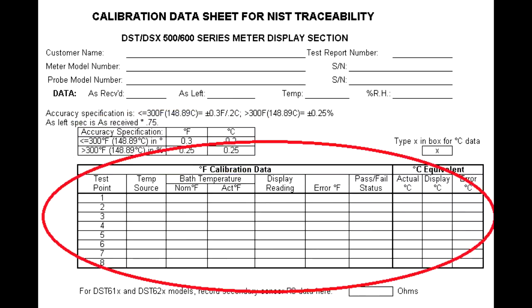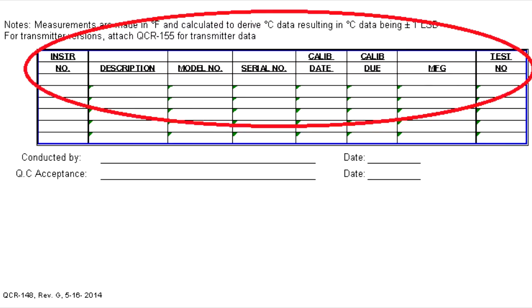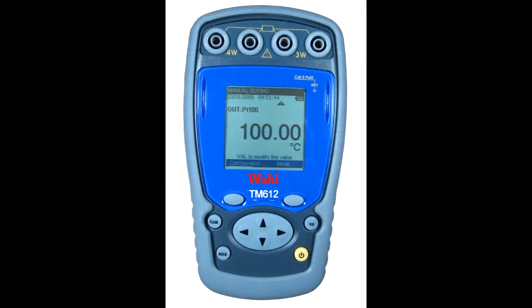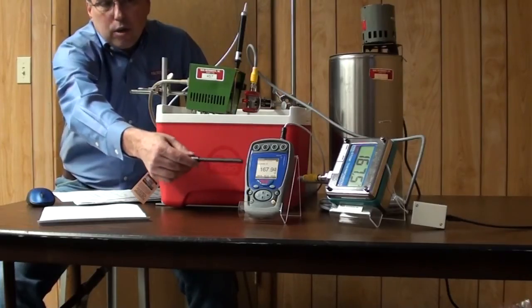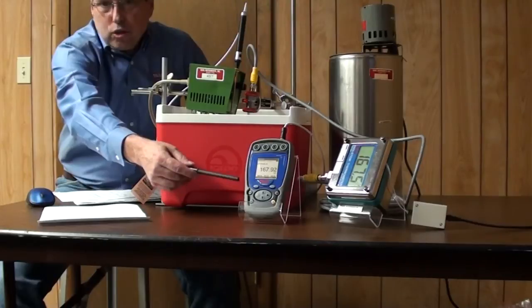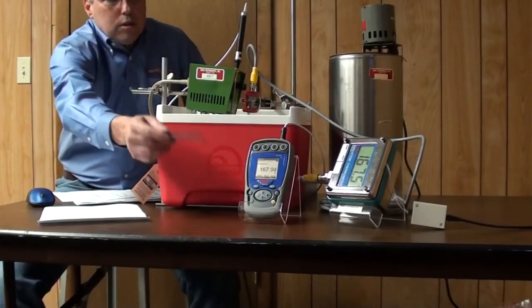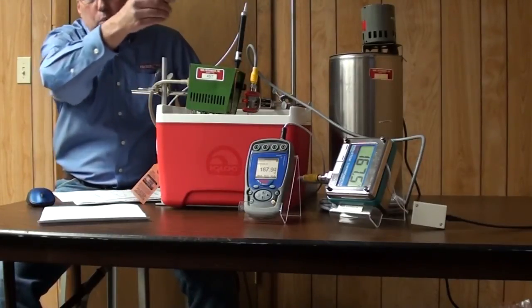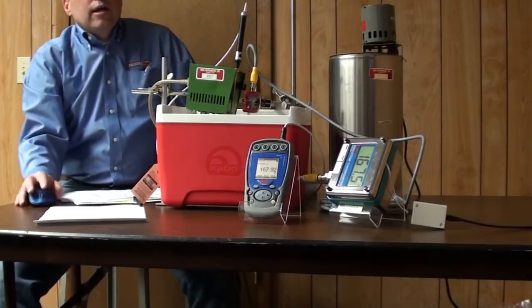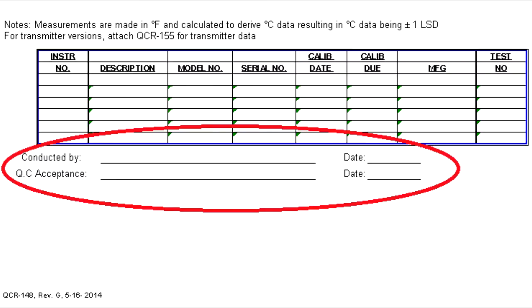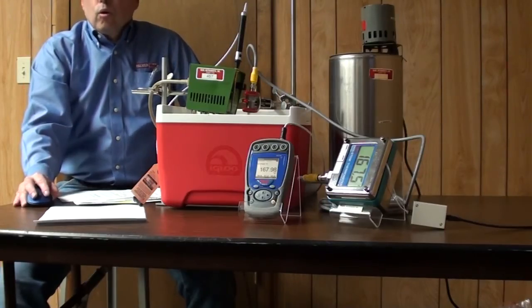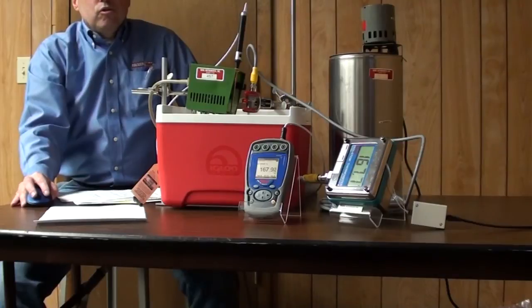And then something else that's required is you have to know what your standard instrument was. In this case, we would be putting our TM612, the information about it, its serial number, model number, calibration date, calibration due date, the test number for it, and description, and then the probe also as part of that. And then down here's where the person performing the test signs, and there's a QC acceptance here for a quality inspector to review all this for accuracy.